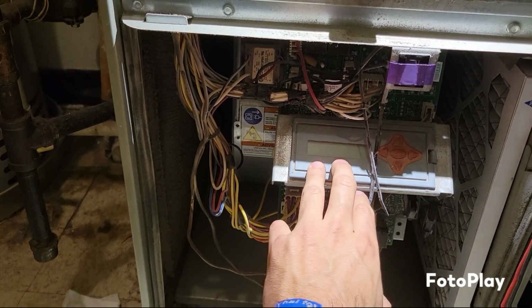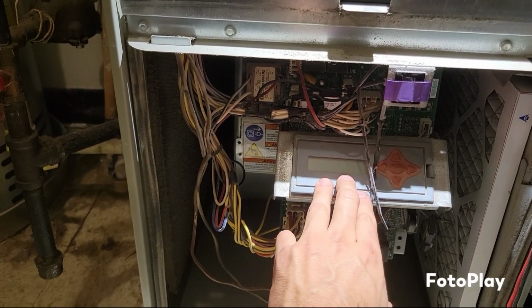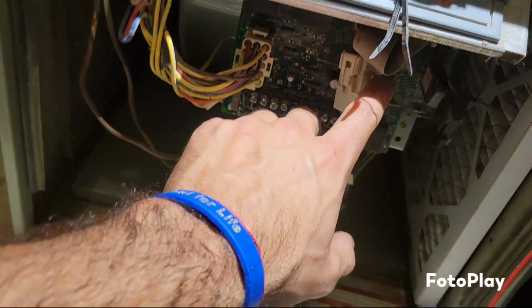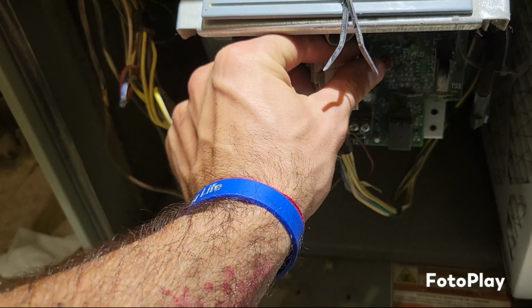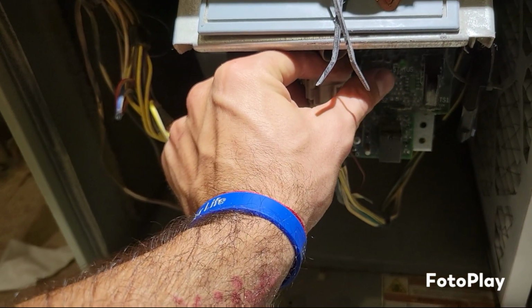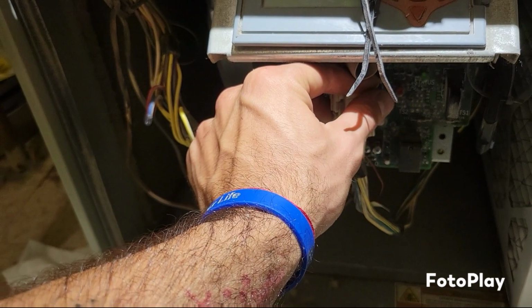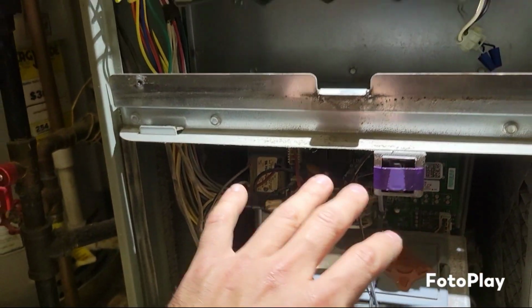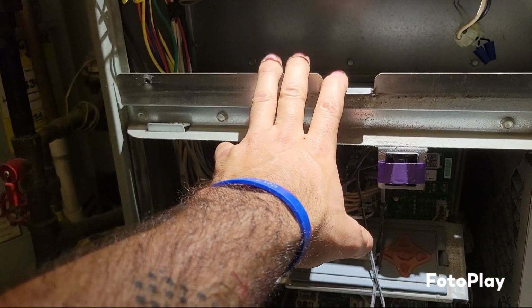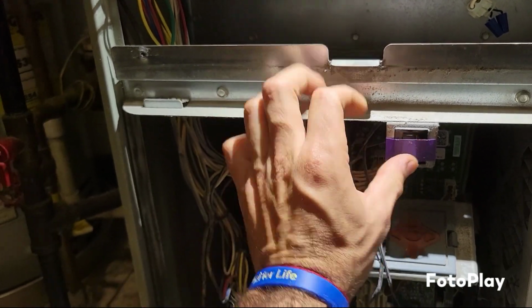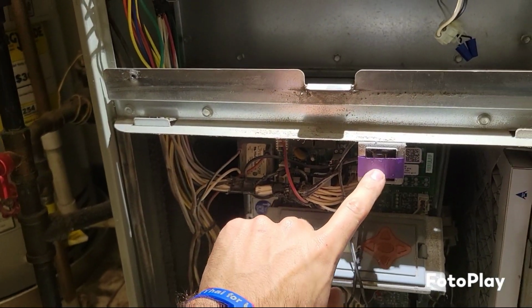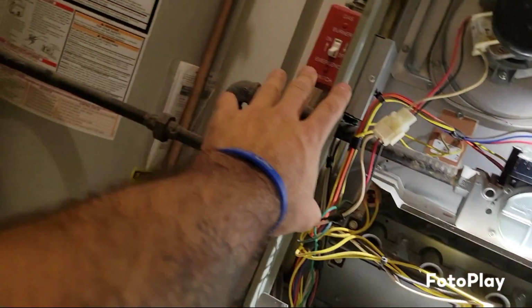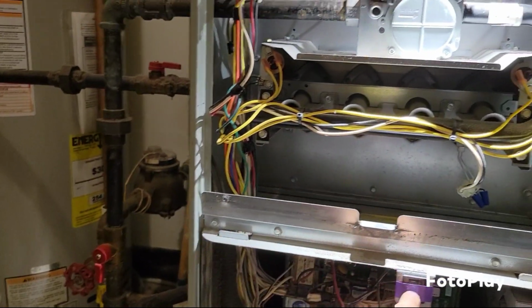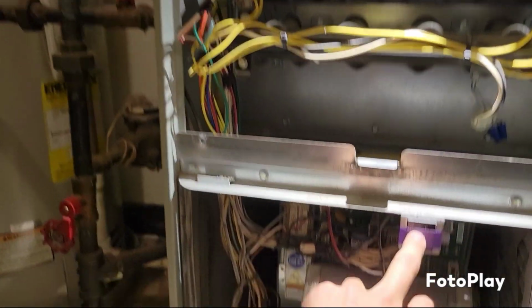But when I reset the system and started recycling, it was basically throwing a 3-blink error code on these lower LEDs located right here, which I know are kind of hard to see, but there are two LEDs. There's a red one and a green one right here. The green represents that there's power present, and then the red one will usually flash and blink a certain number of times before it tells you what particular error code that may be. Now I did this to keep power on, because right now I have the switch off. But yeah, this basically will keep the power on.